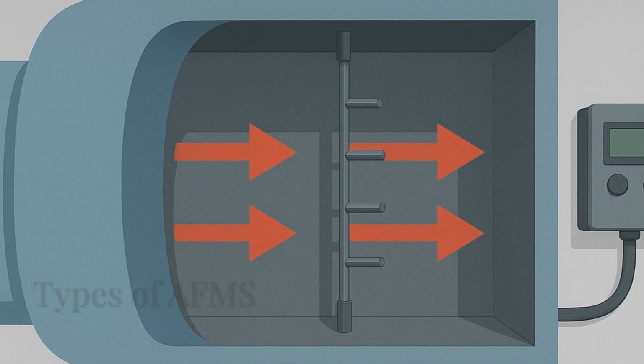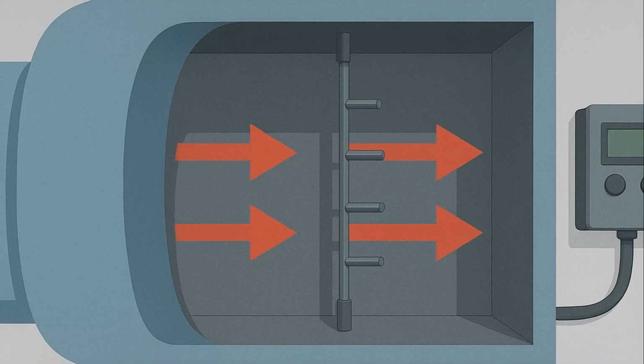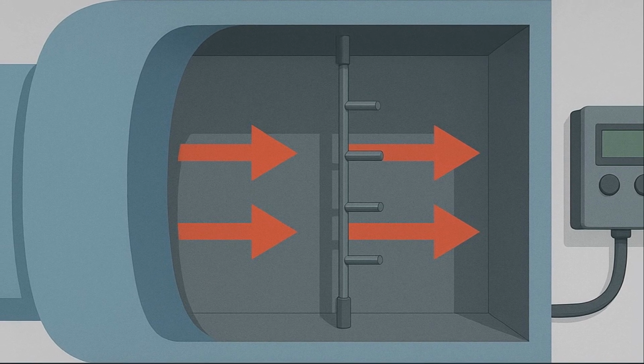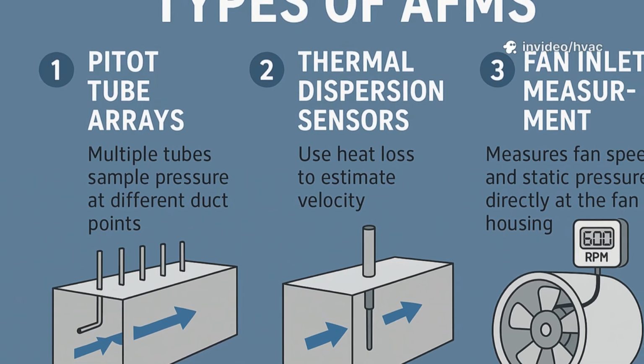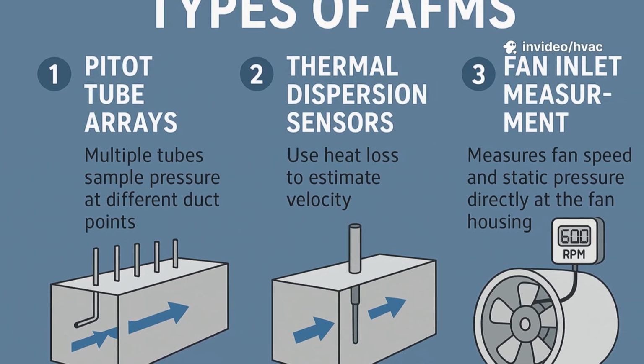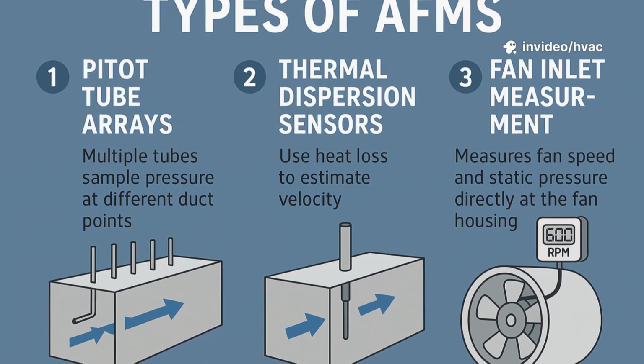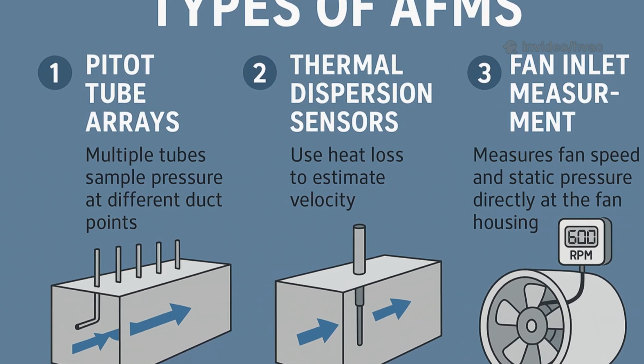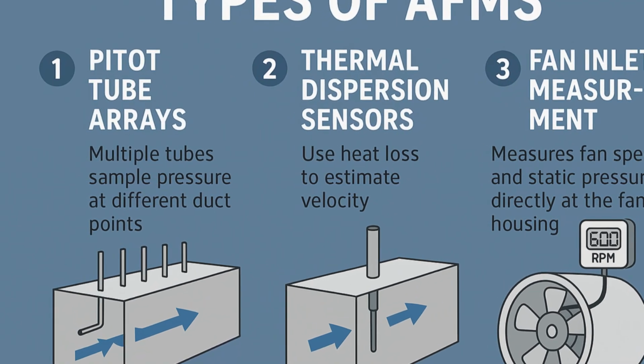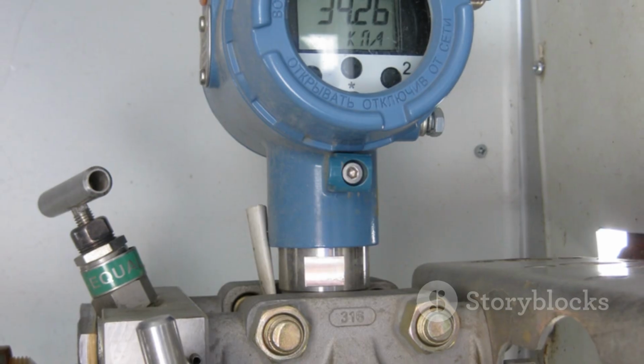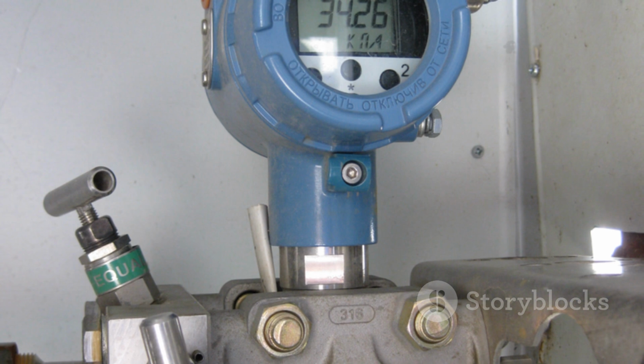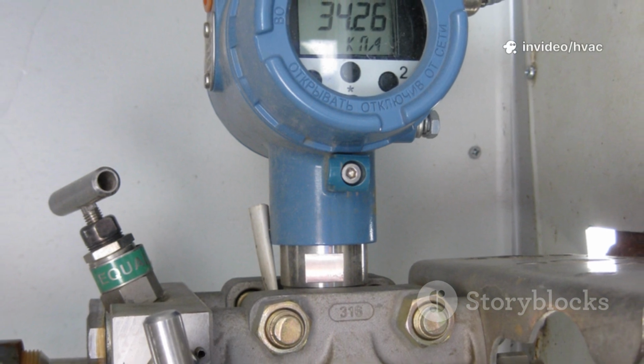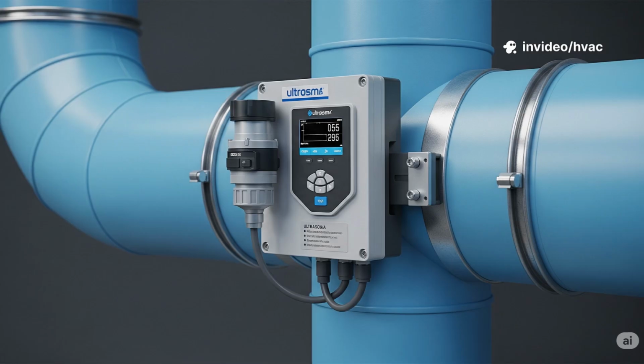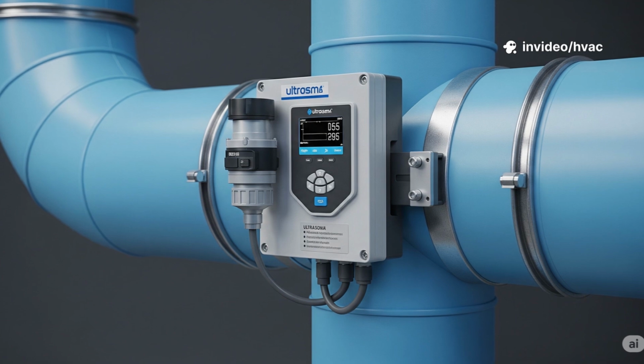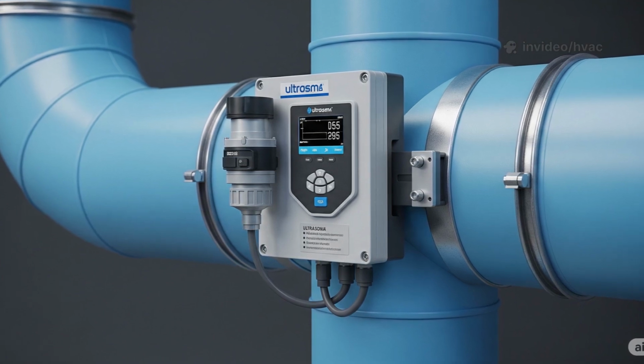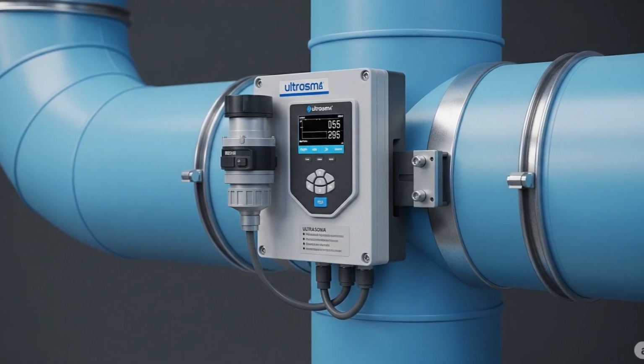Common types include, first, pitot tube arrays, where multiple tubes sample pressure at different duct points. Second, thermal dispersion sensors, which use heat loss to estimate velocity. And third, fan inlet measurement, which measures fan speed and static pressure directly at the fan housing. Additionally, differential pressure sensors are often used to calculate airflow by measuring the pressure drop across a known restriction. Ultrasonic flow meters are another option, using sound waves to determine air velocity without any intrusion into the duct.